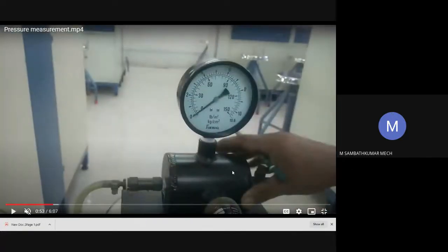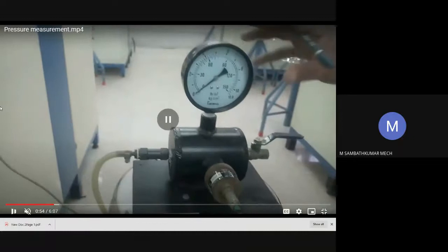So this is the kit, and this is your pressure storage tank, and you know the pressure gauge. The pressure gauge will show the pressure range in that particular place. At the bottom is the sensor, on this side of the drum. The sensor will measure the pressure range and give it in the form of voltage to the pressure measurement trainer kit. So this diaphragm steel sensor is the pressure sensor used to measure the pressure range.